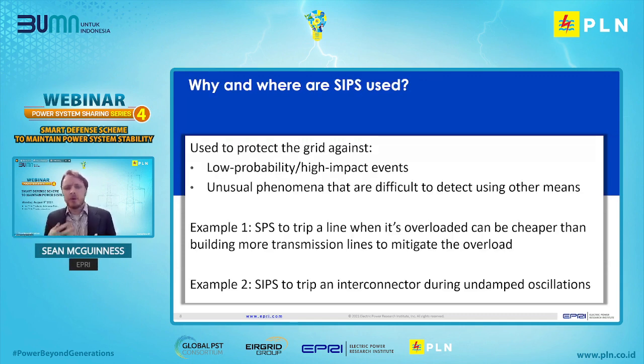Typically, they're deployed where you have low probability and high impact events, such as if you have a risk of overloading a line, but it is very low risk, where it may not justify building additional transmission lines to mitigate that issue. SPS may be installed to trip generators or trip lines to prevent the overload from causing damage, rather than investing in infrastructure.